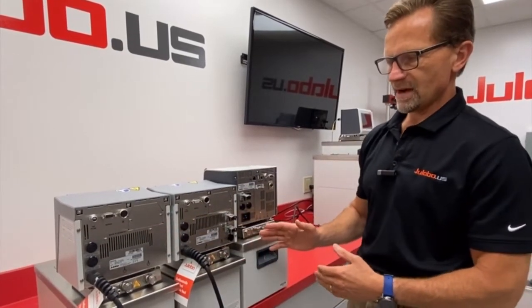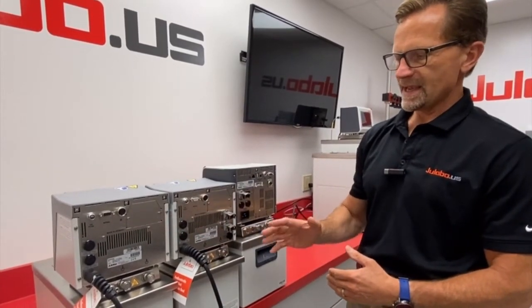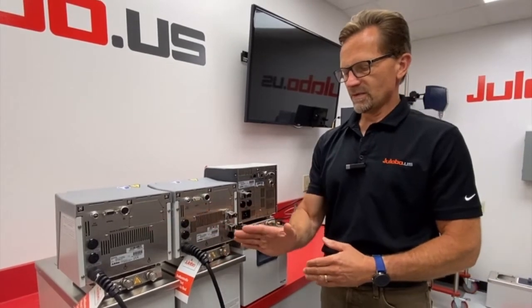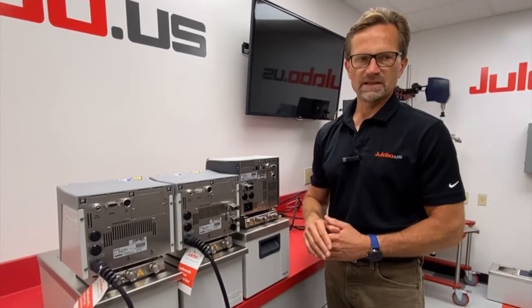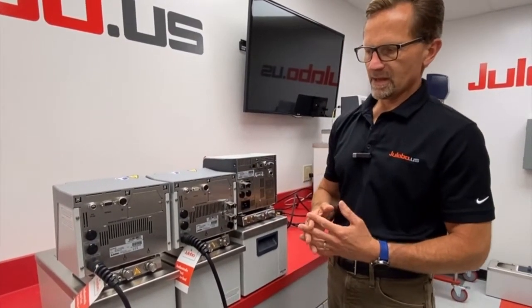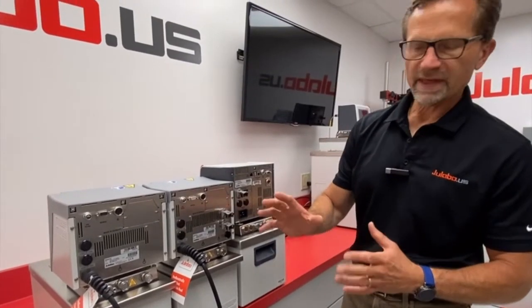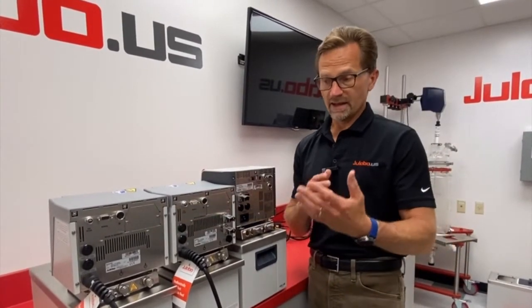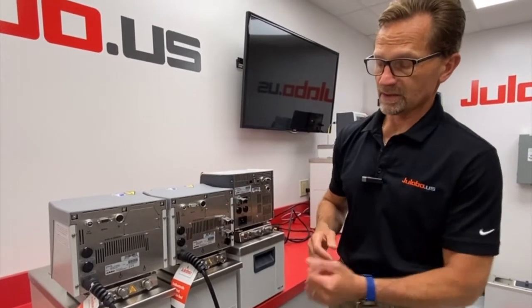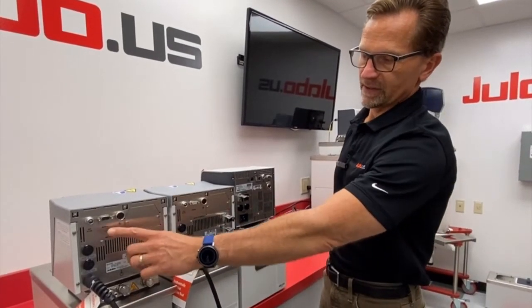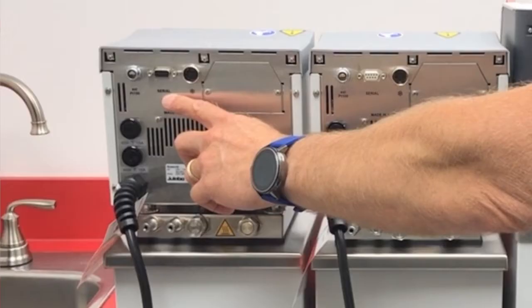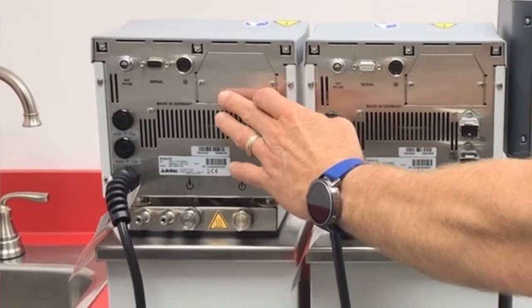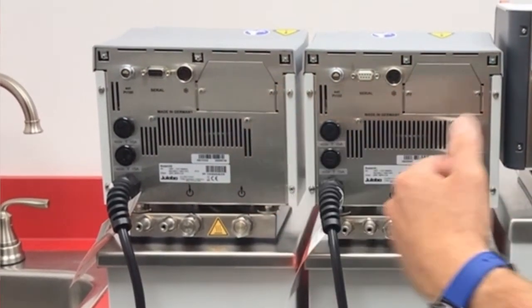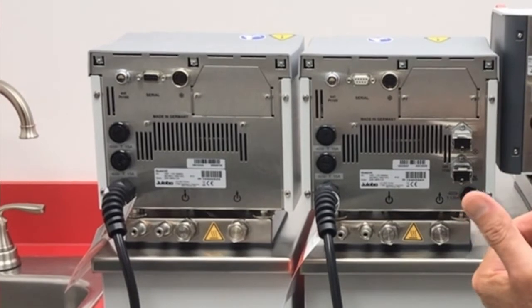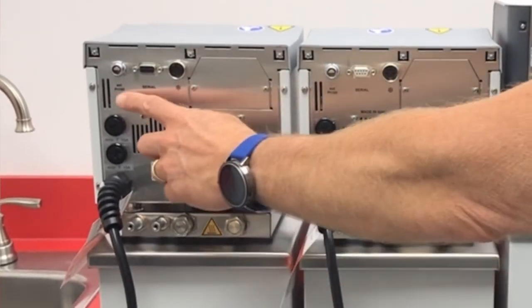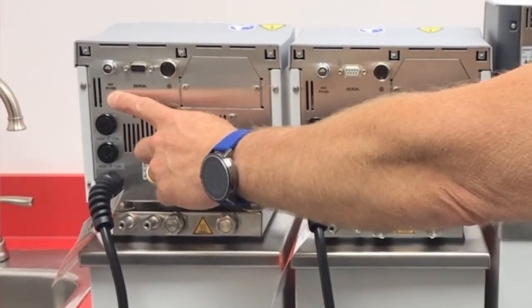All the units that are configured for heating circulators, the HE4, the HL4, and the MSBC4, all have that same combination. Where things change though is when you have the input-output options for the models. On the HE, you have a serial port, which is RS-232 only, and a slot for an optional analog module if you want to communicate via voltage or current. You also have an external PT100 sensor port.